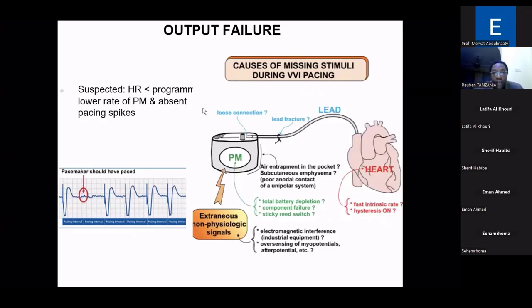So with the mechanical complications, one can be output failure, which causes missing stimuli during VVI pacing, and is suspected when the heart rate is lower than the programmed lower rate of the pacemaker, or when you have absence of pacing spikes. As you can see on the left side, the pacemaker is supposed to pace, but it's not pacing. So this is output failure.